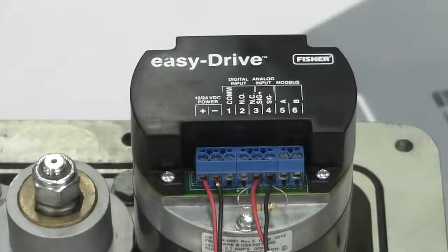Shielded signal wire is preferred in all installations and should be grounded at the signal source. The Easy Drive can communicate with either 4 to 20 milliamp or 1 to 5 volt input signal. If the signal source is 1 to 5 volts, then the 250 ohm resistor needs to be removed. Once the cables have been secured to the terminals within the Easy Drive, you can now apply power to the unit. Once power has been applied to the unit, the signal can then be sent to the actuator.